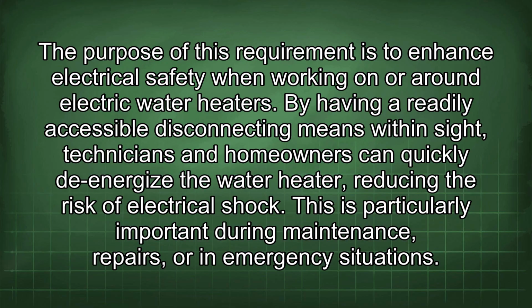The purpose of this requirement is to enhance electrical safety when working on or around electric water heaters. By having a readily accessible disconnecting means within sight, technicians and homeowners can quickly de-energize the water heater, reducing the risk of electrical shock. This is particularly important during maintenance, repairs, or in emergency situations.